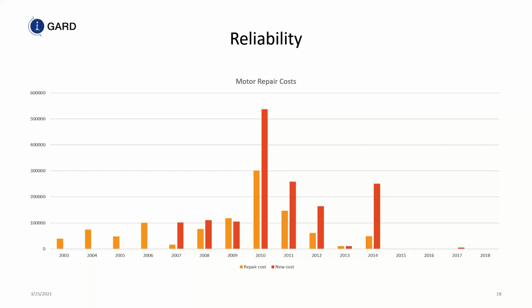Now this was done in 2010 through 2014. So at the time that they did this, they were following the 2004 guide for calculating arc flash incident energy. And unfortunately, during that time, because 1584 penalized high resistance grounding by assigning a higher incident energy than a solidly grounded system, which is not true, it has been rectified, they decided that it was worth their while to change 100 substations from solidly grounded to resistance grounding as an arc flash mitigation technique and install some arc flash mitigation relays to reduce the time that the fault was on the system.